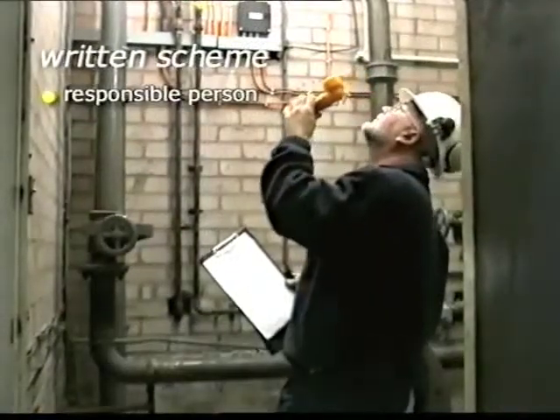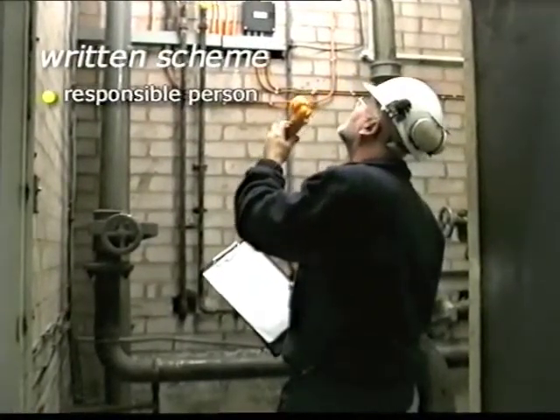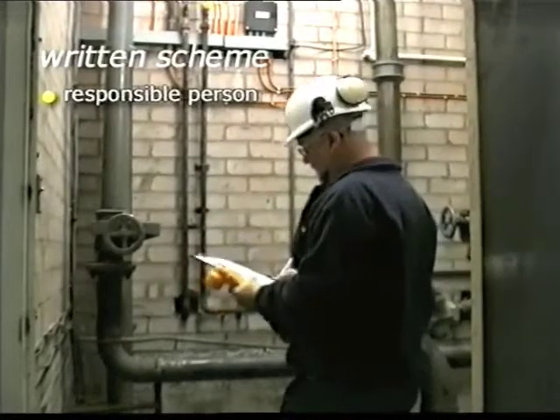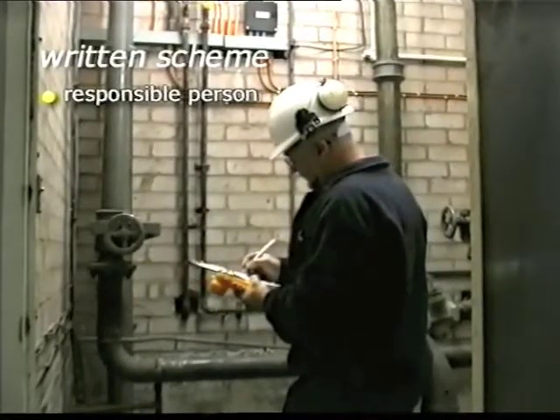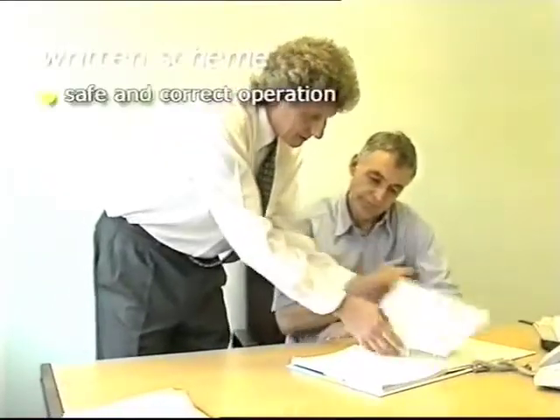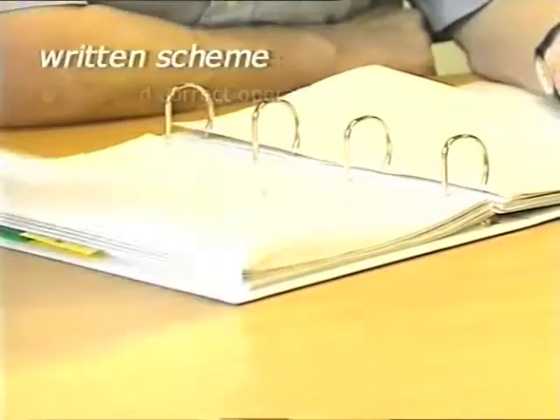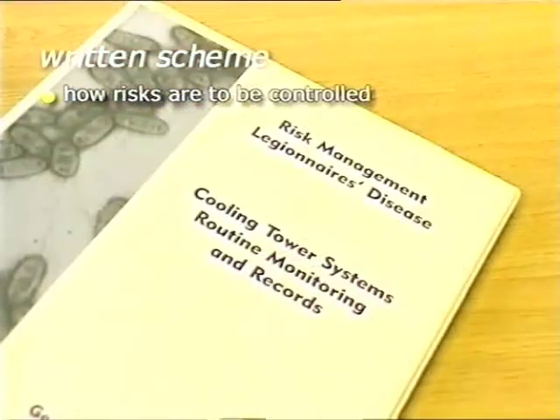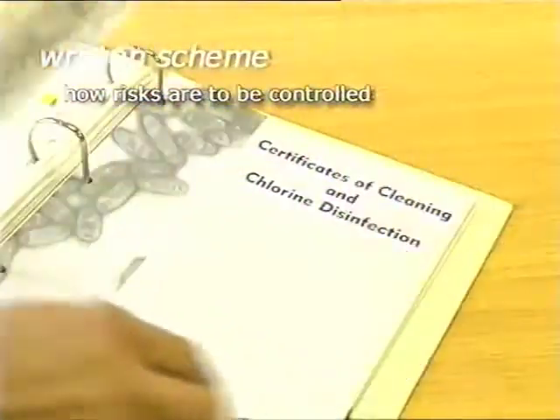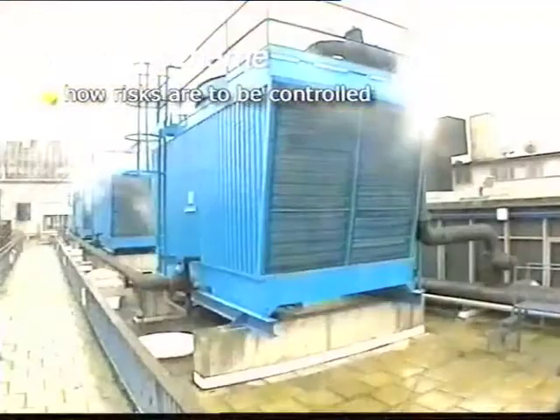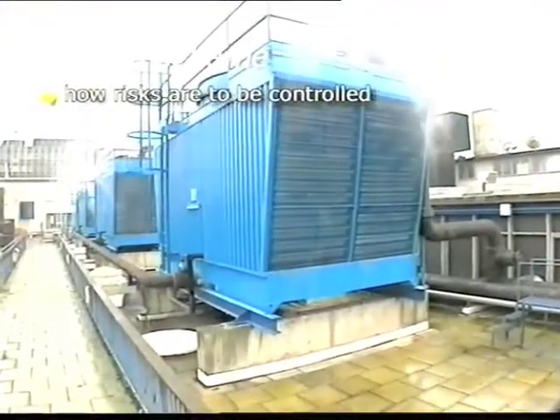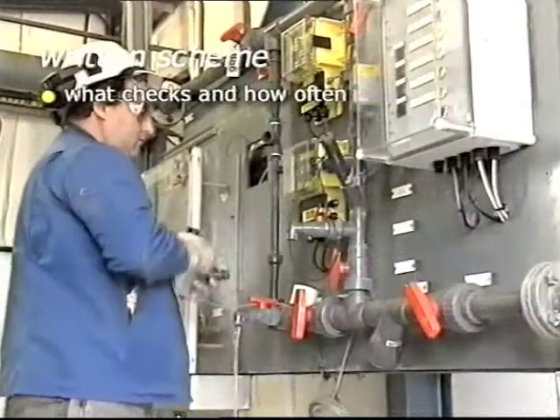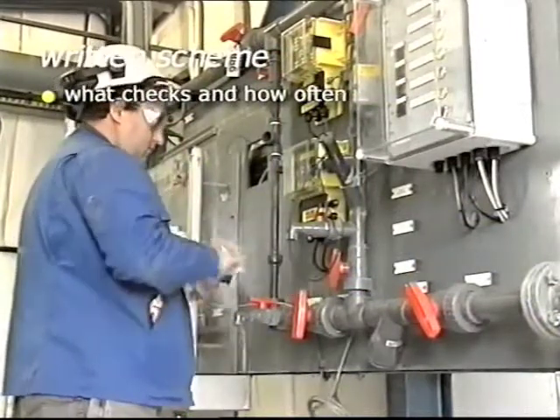The details of who carried out the assessment and who is responsible for managing the control scheme. This person is referred to as the responsible person, and they must have sufficient authority, competence and knowledge to make sure the control scheme is managed effectively. A description of safe and correct operation of your system. The details of how risks from Legionella are to be controlled. For example, what water treatment regime you will be using, or how you intend to control release of water droplets. The checks that you will make on control regimes and how often these will be carried out.